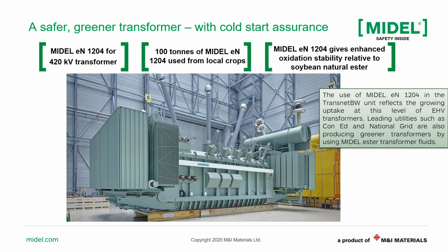And one reason the utility decided to use this liquid is that MIDEL EN1204 has a lower pour point, so it can operate to -31 without any issues, especially in Europe, where you have high cold temperatures. Also, as a natural ester, it has double the oxidation stability of MIDEL EN1215, which is our soybean-based natural ester. So the preferred option is to use MIDEL EN1204. The utility is TransnetBW, which is, I think, a German transmission utility. This indicates that utilities are using natural esters in very high voltage transformers, indicating that the technology is maturing more and more by the year. This is our first case study.